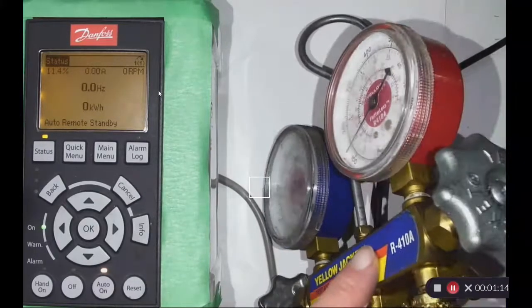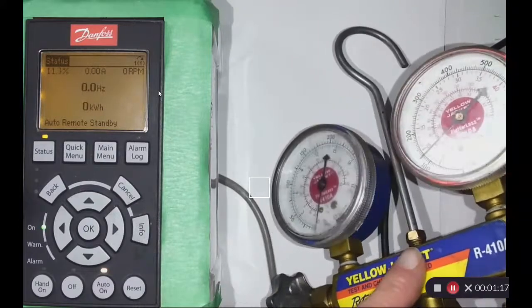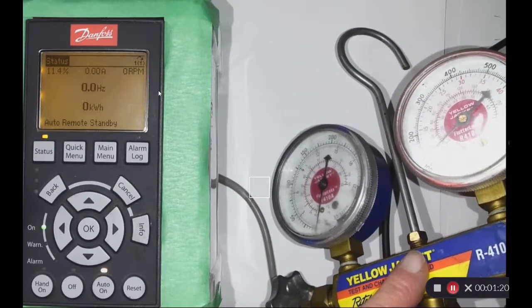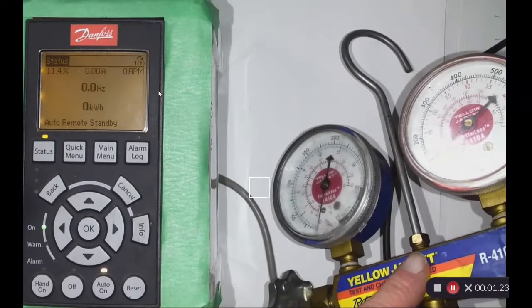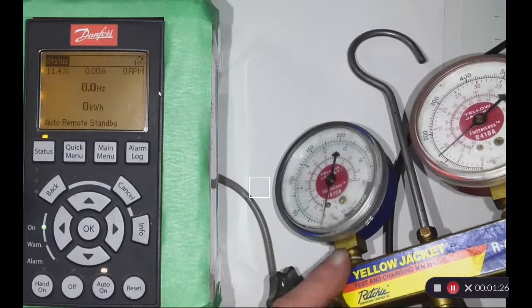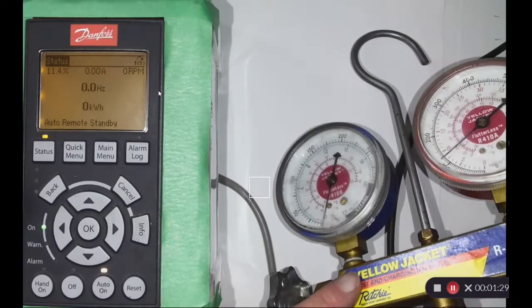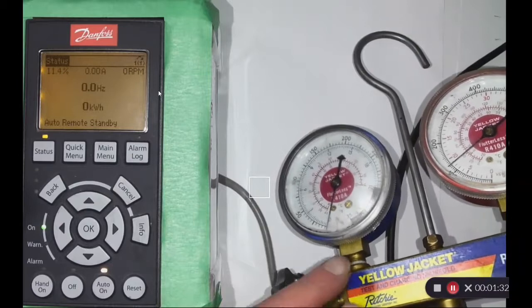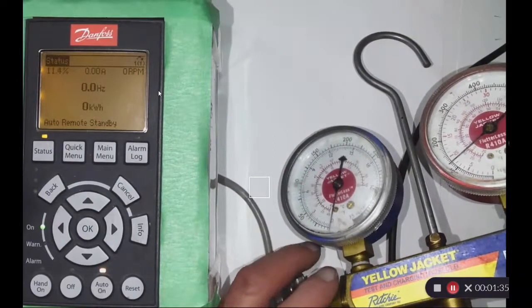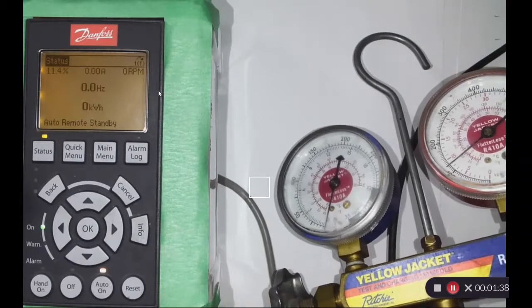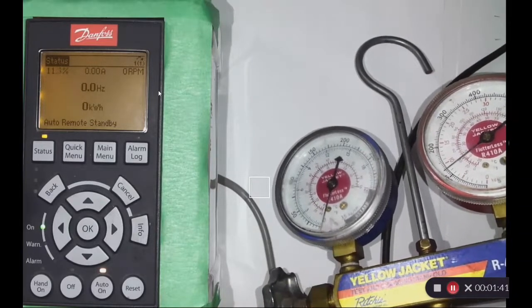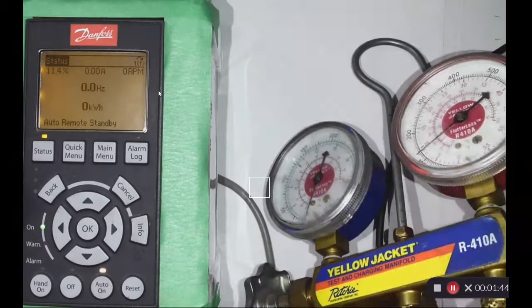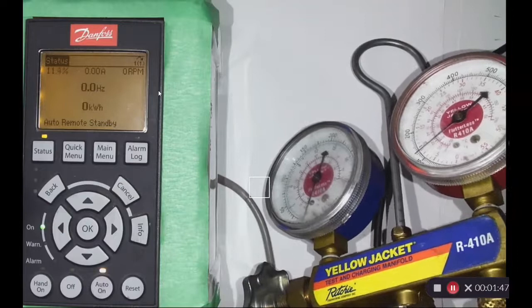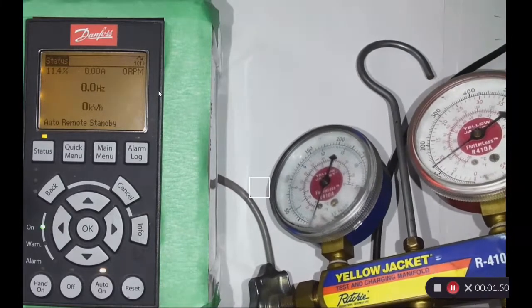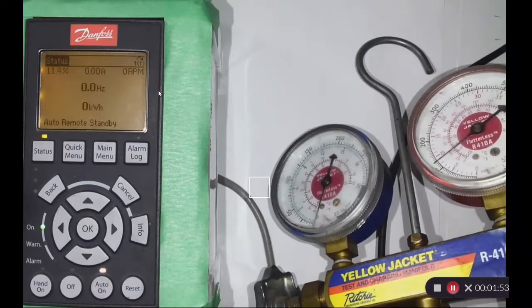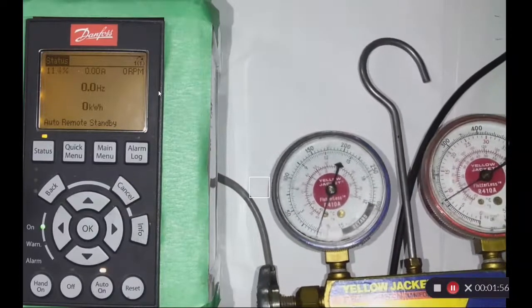So when I roll that tap open on the right-hand side, it's going to take pressure and put it onto the pressure transducer. And if I want to see what that pressure is, I'm not hooking my low side gauge, the blue hose, to a refrigeration system. If I did and I wanted to see the low side gauge pressure, then I would open the low side, the left side tap, and I would see the low side pressure right straight through to the gauge, and I would see my high side pressure right straight to the gauge from the red hose.